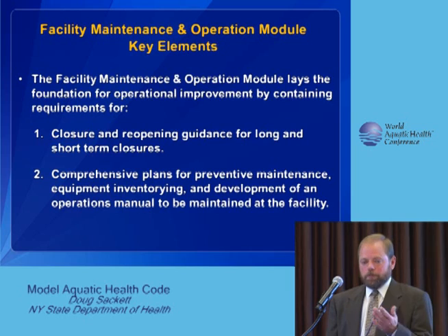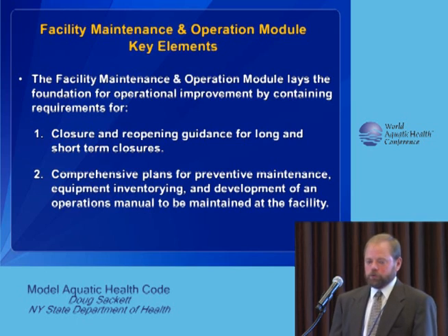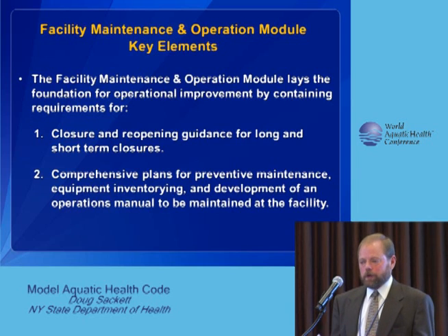If you heard Michelle Lavsa's presentation on inspection problems, what do you find? Inadequate or absent chlorine residuals. Very often you'll find out that the chemical feeder is not working. Take an example of a peristaltic type feeder. Those tubes are only good for a certain period of time. If that tube ruptures, if it's not replaced routinely, it's set up for failure.